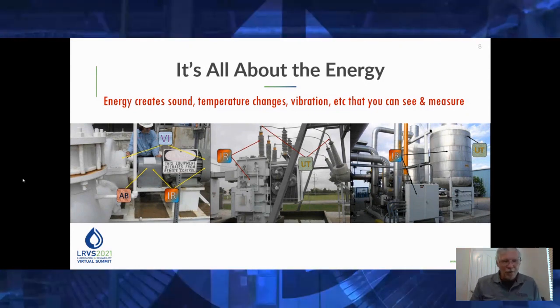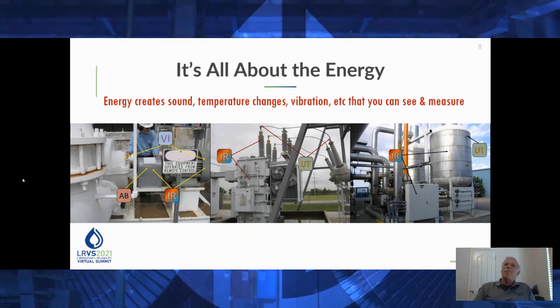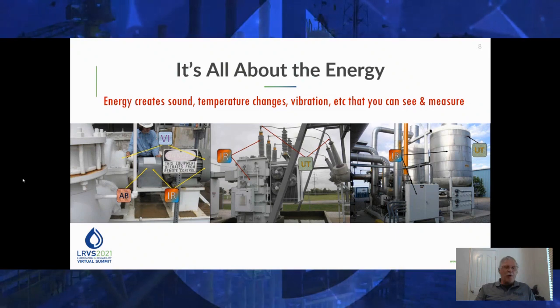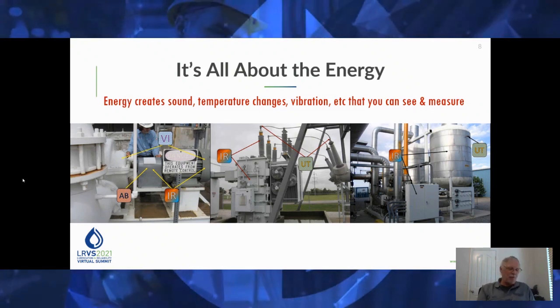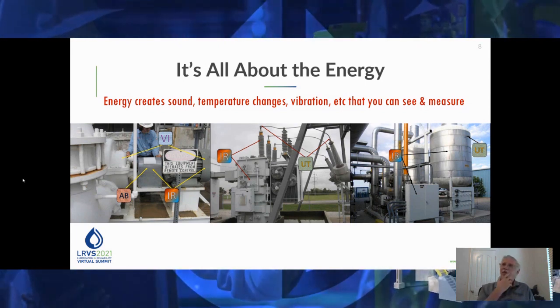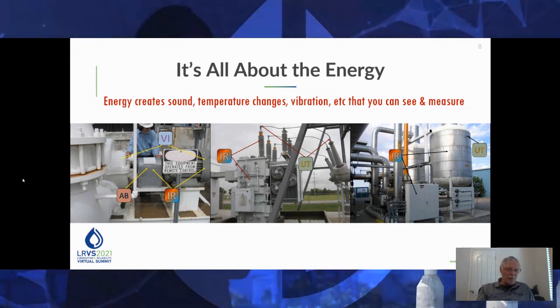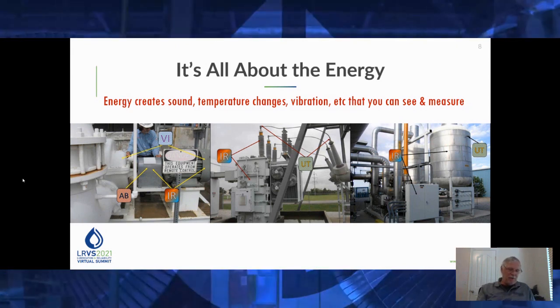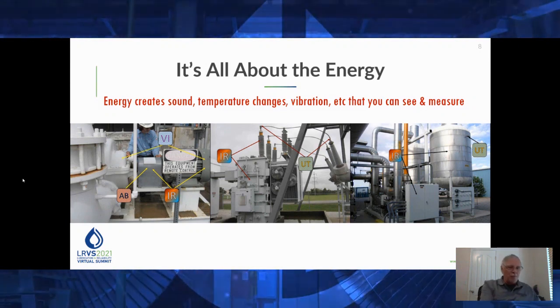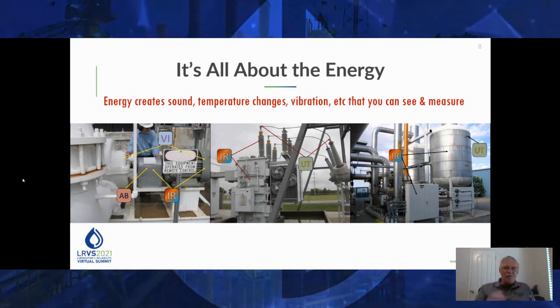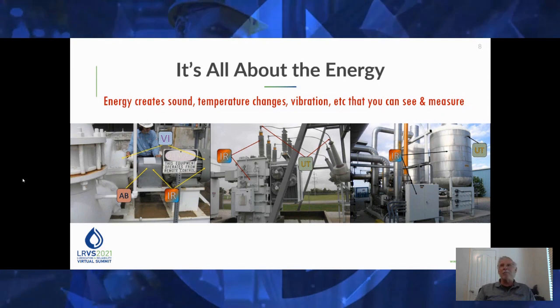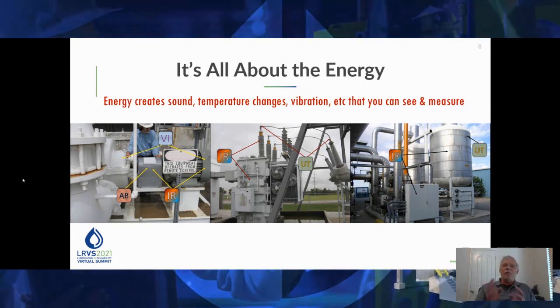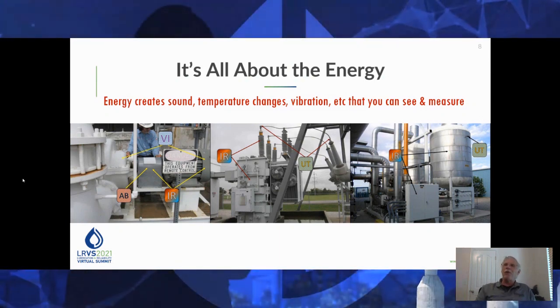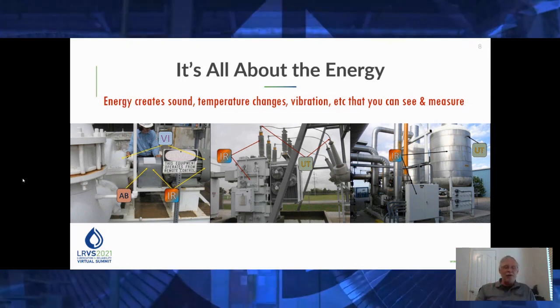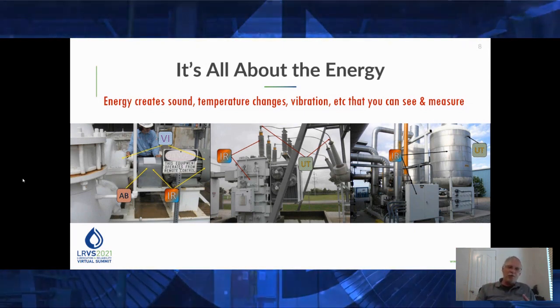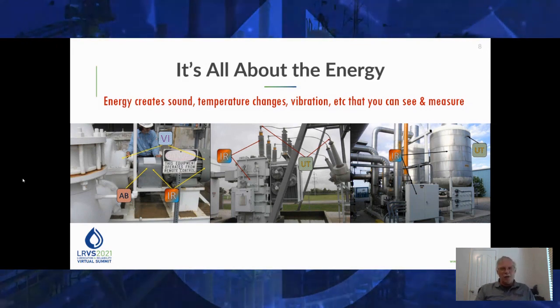And so here's where I was talking about knowing your process and knowing your system. If you know that there is supposed to be a temperature gradient from the top to the bottom of that vessel, but you do an infrared survey and there's not, you've identified a problem. If you look at that and there's a big red spot right in the middle where there's supposed to be nice, even insulation, you know you have an insulation problem. If you didn't know how that process worked and you took a picture of it and it was all nice and even and the same temperature, except it was 70 degrees and it's supposed to be 180 degrees, you'll never know that you had that problem.